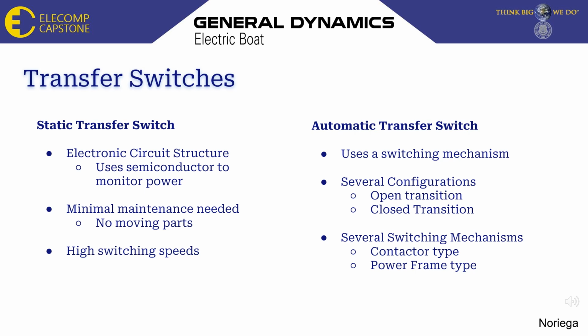Automatic transfer switches use a switcher mechanism to switch between power sources, and these typically have several configurations such as closed and open transition, using several switch mechanisms such as those in contactor and power frame type automatic transfer switches.